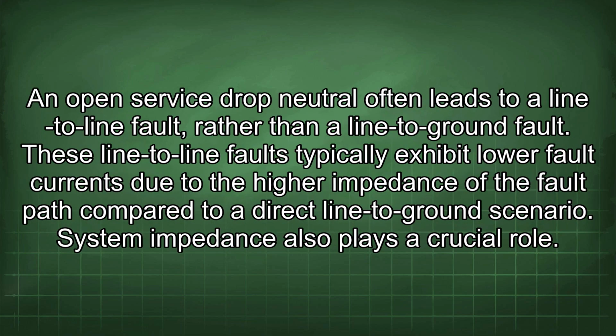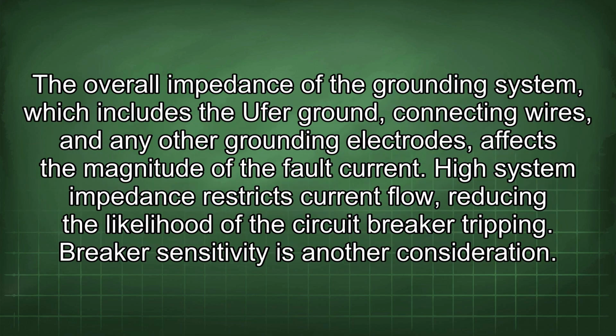An open service drop neutral often leads to a line-to-line fault, rather than a line-to-ground fault. These line-to-line faults typically exhibit lower fault currents due to the higher impedance of the fault path compared to a direct line-to-ground scenario. System impedance also plays a crucial role. The overall impedance of the grounding system, which includes the Ufer ground, connecting wires, and any other grounding electrodes, affects the magnitude of the fault current. High system impedance restricts current flow, reducing the likelihood of the circuit breaker tripping.